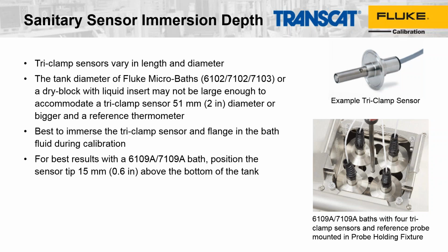We recommend that, if possible, if the sensor is long enough, it is immersed until it's just a little over a half inch above the bottom of the tank. But not all sensors are long enough to do that. We recommend that minimally the sensor is immersed so that the flange is down inside the fluid, just to help prevent heat loss. If the sensor happens to be much longer, like 6 inches in length, the sensor sheath, then it's probably not necessary. Well, actually, I should say it's not possible to put the flange down into the bath fluid. But for shorter sensors, it's recommended to allow the flange to go right into the fluid, as shown here in these pictures.